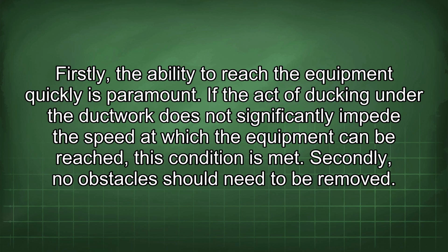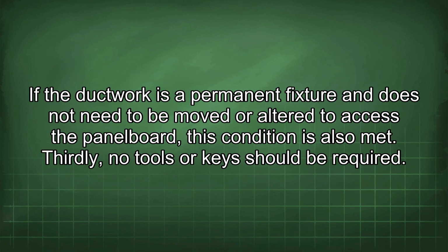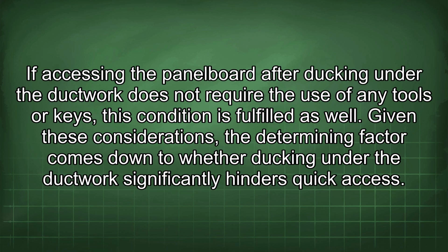If the act of ducking under the ductwork does not significantly impede the speed at which the equipment can be reached, this condition is met. Secondly, no obstacle should need to be removed. If the ductwork is a permanent fixture and does not need to be moved or altered to access the panel board, this condition is also met. Thirdly, no tools or keys should be required. If accessing the panel board after ducking under the ductwork does not require the use of any tools or keys, this condition is fulfilled as well.